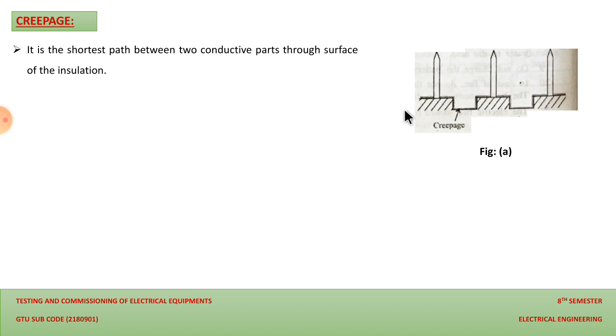Now let us discuss the second, that is creepage. So what is actually creepage? Here you can see in this diagram we have placed electrodes like this, and between the electrodes we have an insulating material which is provided to the ground. So it is the shortest path between two conductive parts through the surface of the insulation. This is the surface where insulation is provided, and if we keep a short distance between two conductive parts, then there might be chances of creepage.